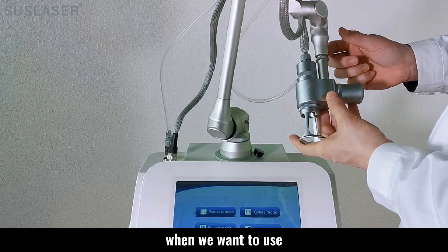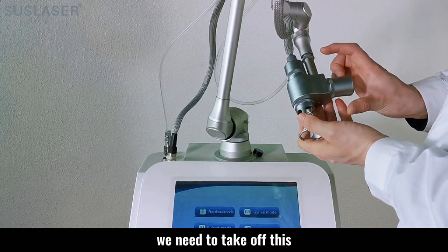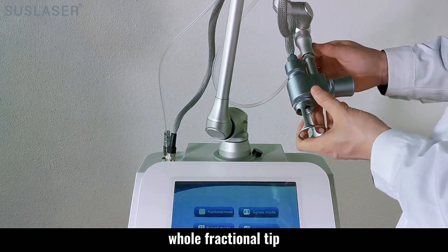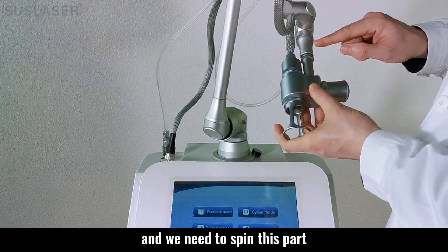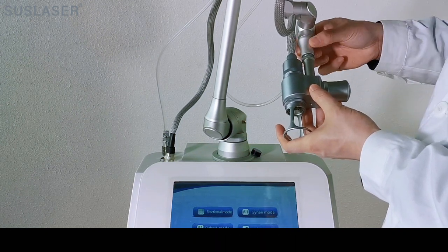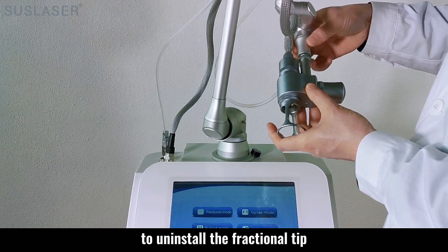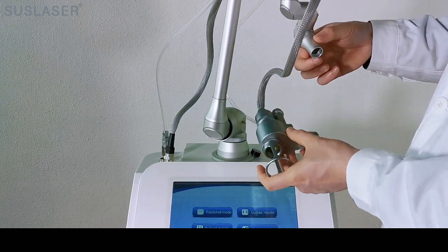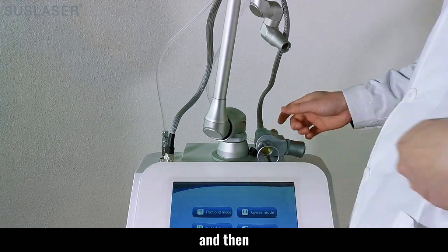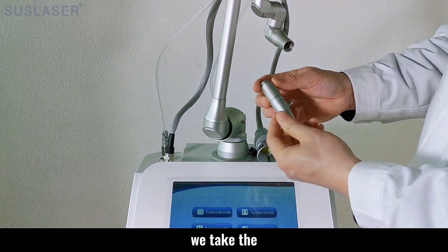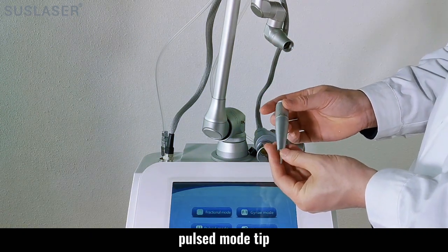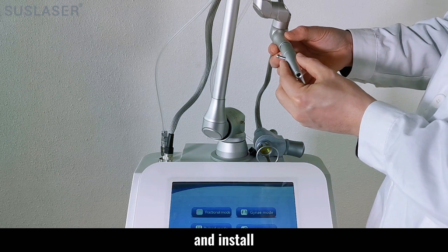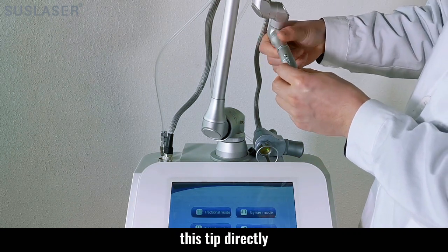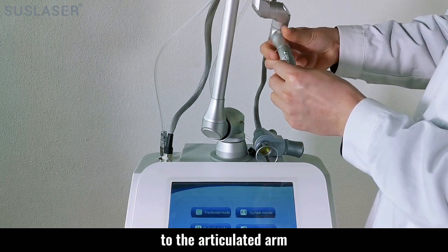When we want to use the pulse mode, we need to take off this whole fractional tip, and we need to spin this part to uninstall the fractional tip. Then we take the pulse mode tip and install it directly to the articulated arm.